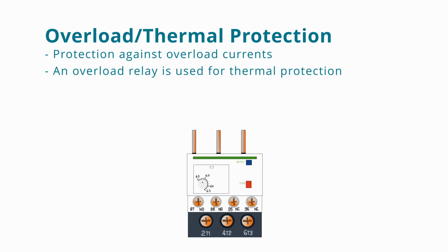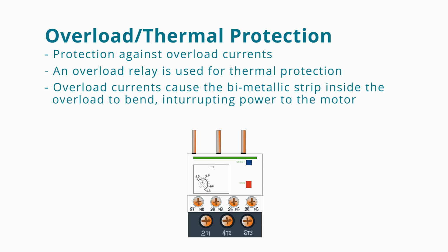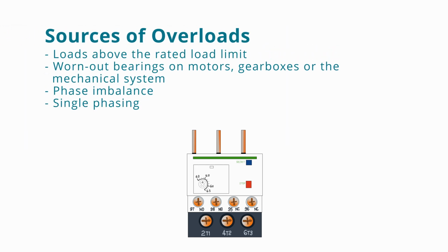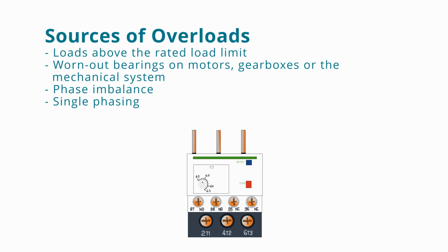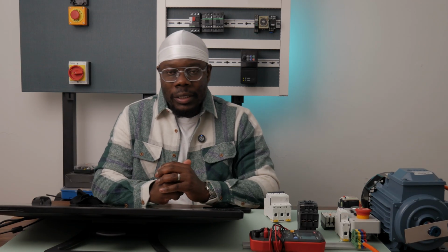An overload relay protects the motor windings against overload currents. Inside, it has a bimetallic strip which relies on the thermal effect of current. When current that is more than the rated current of the electric motor flows for prolonged periods, the bimetallic strip bends, activating contacts on the control circuit that will interrupt power to the motor. The overload relay allows us to set the approximate tripping threshold for an electric motor. General circuit breakers offer thermal overload protection, but their response to small overload currents is much slower. Sources of overloads in electric motors include motors driving a load that is above their load limit, worn-out bearings on motors, gearboxes or the mechanical system, phase imbalances in electric motors, and single phasing. I hope this gives you an idea of overcurrent protection in electric motors.